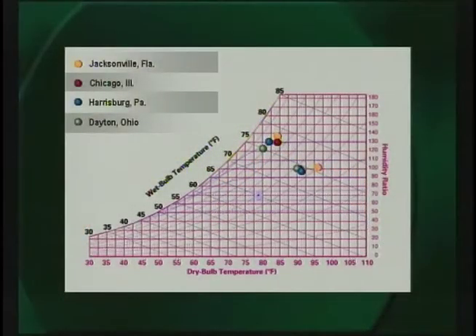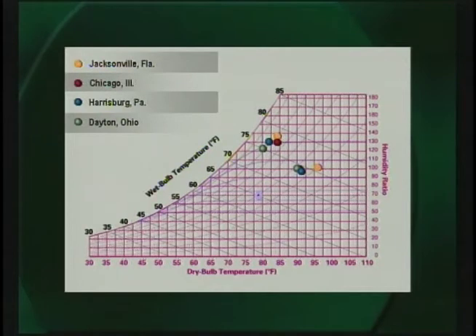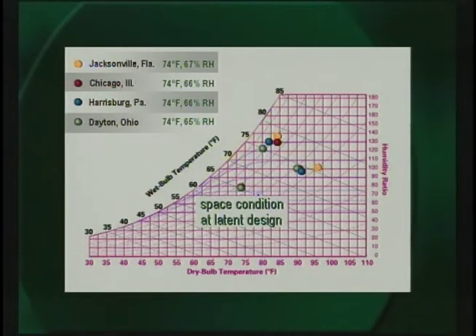For our discussion today, it's important to remember that peak sensible load rarely occurs at the same time as peak latent load. In John's Jacksonville example, sensible peak occurred at dry bulb temperatures of 96 degrees and higher, while latent peak occurred at an average dry bulb of 84 degrees — definitely different days. This brings up a common misconception that space humidity control is only a concern in the humid climates of the southeastern United States. Here are the outdoor sensible and latent design conditions for Chicago, Illinois; Harrisburg, Pennsylvania; and Dayton, Ohio. The design conditions are not all that different — space conditions would be acceptable at sensible design, but would present a problem at latent design conditions, with space relative humidity ranging from 65 to 67 percent, regardless of location.